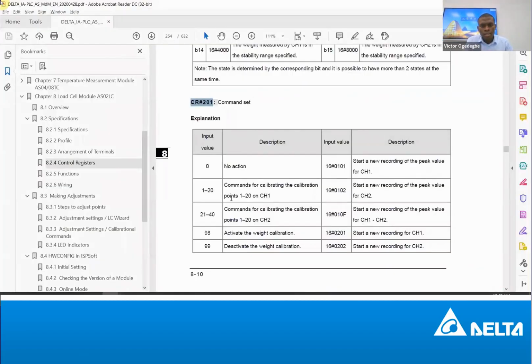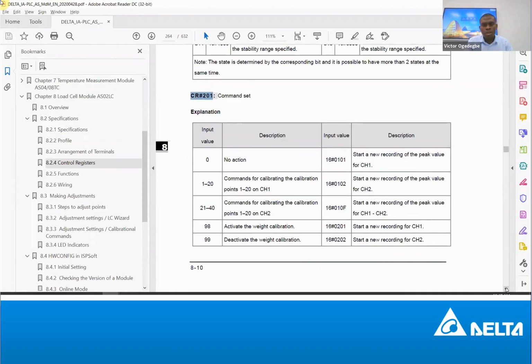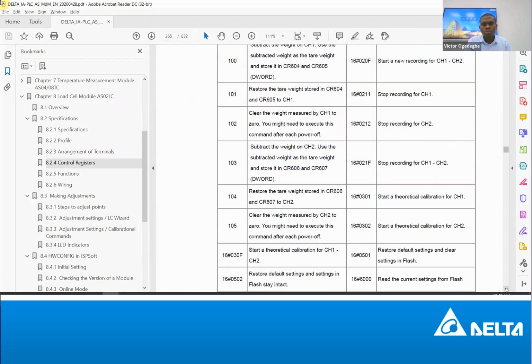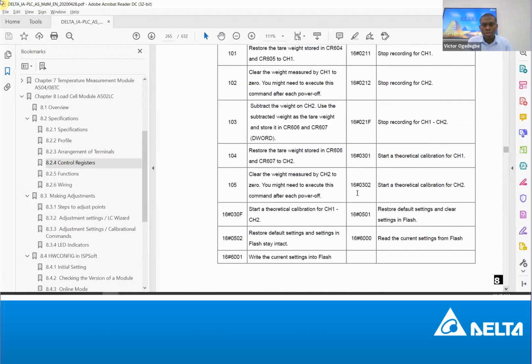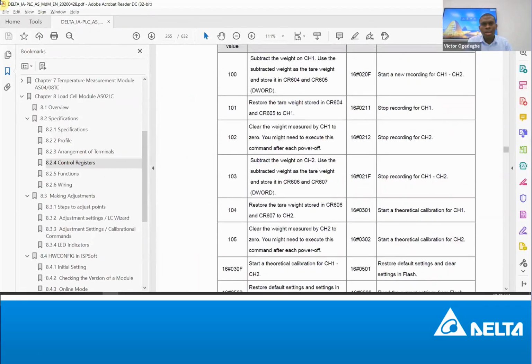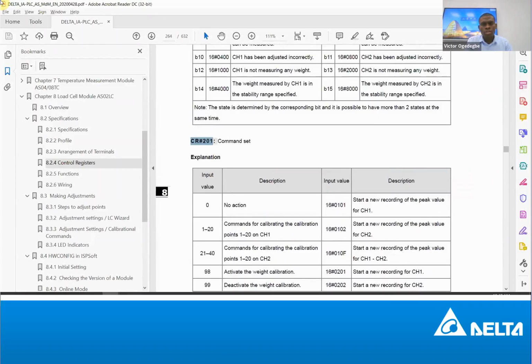So let's go back. So you see there are different commands like 98. That's what I meant. If you write 98 to this register, it means you want to start calibration. If you write 99, you want to deactivate calibration. So there are different commands, very many that you can write. Depending on what you want to do, you write a command to this register, and then the module starts behaving according to the command that you have written.